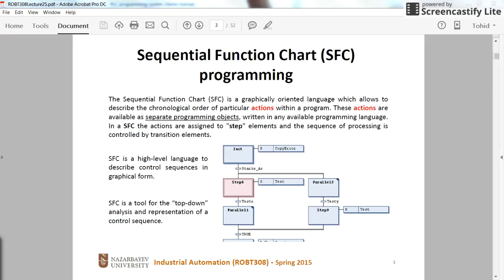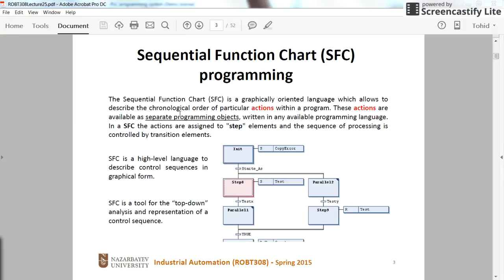Hi everyone. In this short video I am going to introduce another programming language for the PLC which is called SFC, or Sequential Function Chart. Sequential Function Chart is basically a graphical chart which contains steps as the main elements, the transitions between the steps, and also the actions which can be taken along with the steps — during the step, whenever you enter the step, or whenever you exit the step.